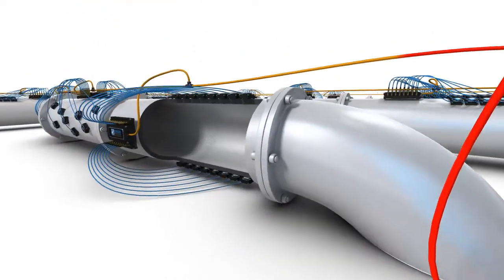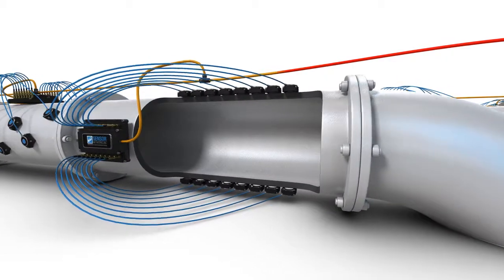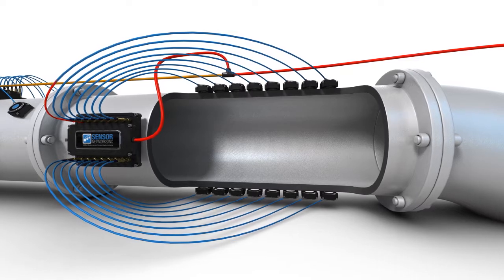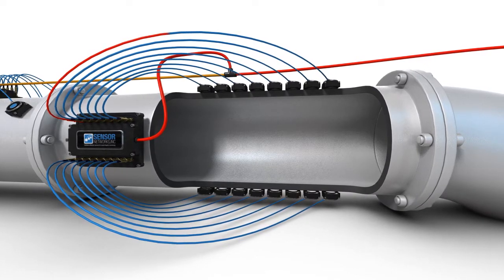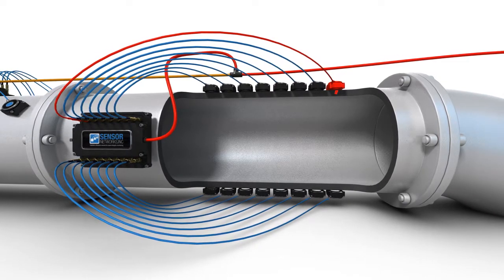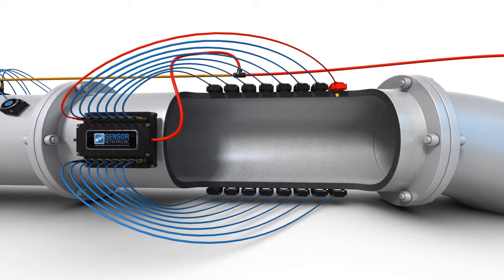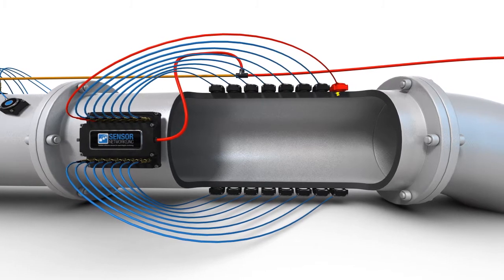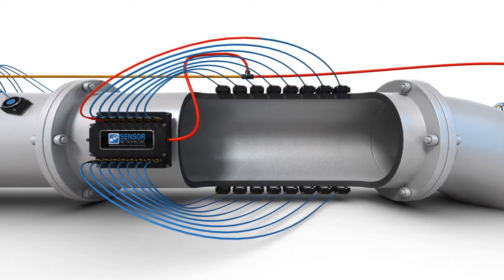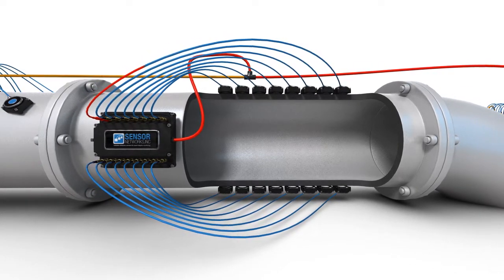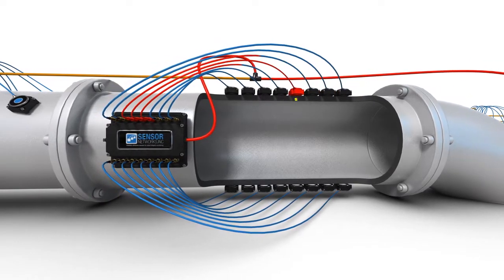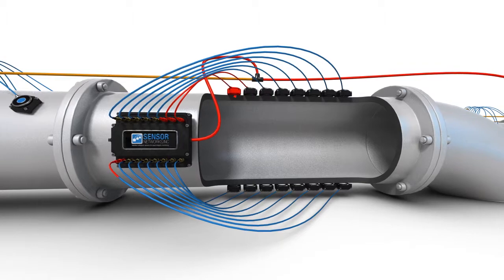The system initially prompts the first DSI to gather ultrasonic thickness measurements from up to 16 connected transducers. The DSI sends an ultra-short analog pulse to the first connected transducer, where it is converted into high-frequency acoustic, or ultrasonic, energy. That energy travels through the subject material and reflects off the back wall. The signal from the reflection is converted by the transducer back into an RF electrical pulse, and then digitized by the DSI.